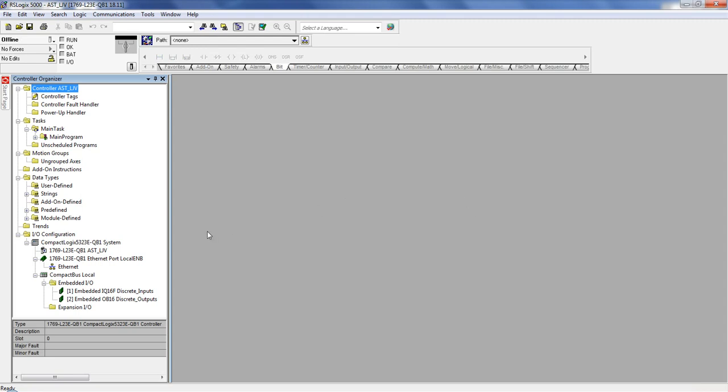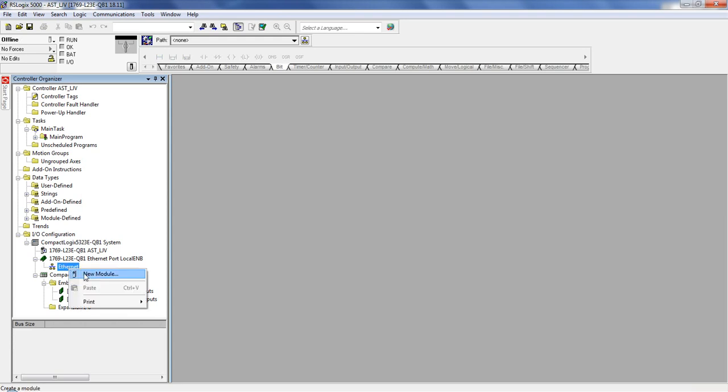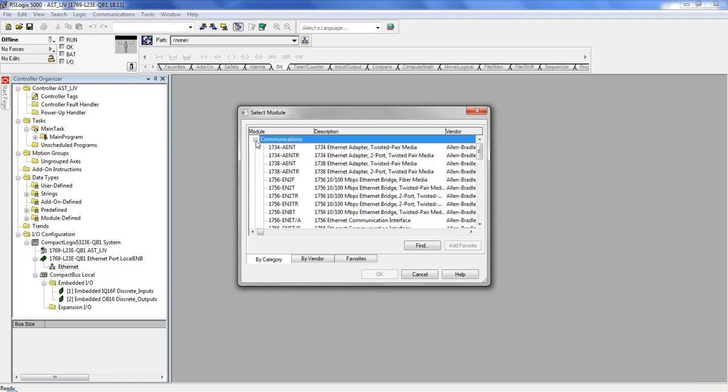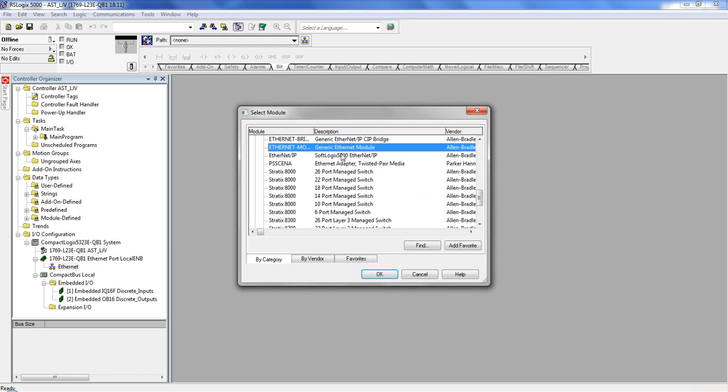All right, so simply to connect to our CBEP100 module, you go to I.O. Configuration. We go under our PLC, and we find Ethernet. Once we get to Ethernet, we right-click, New Module. And for all of our units, we always choose it to be a generic Ethernet module. So here we find that, click OK.